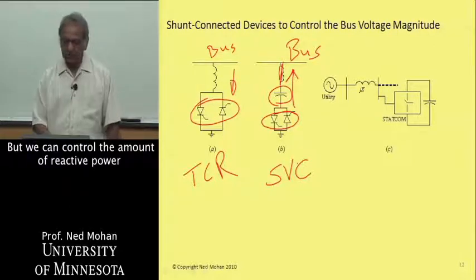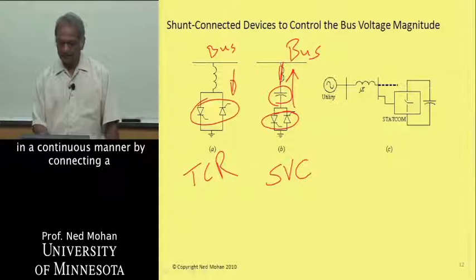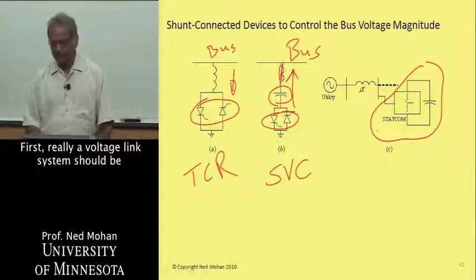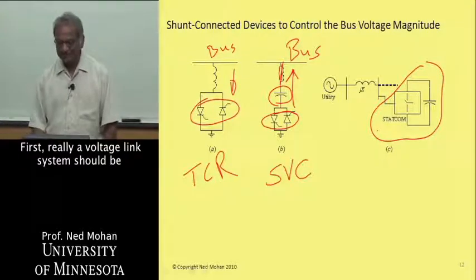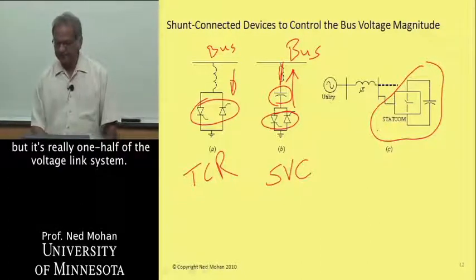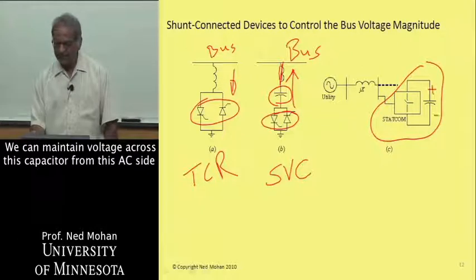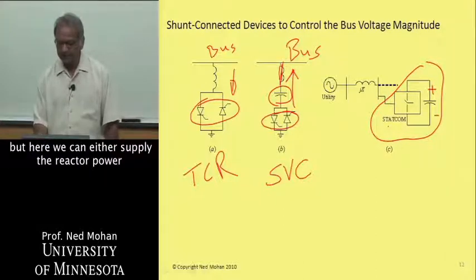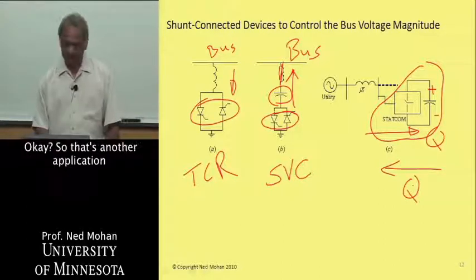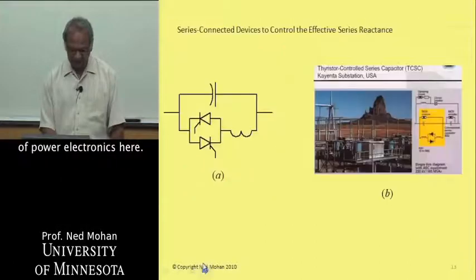We can control the amount of reactive power continuously by connecting a static compensator, or STATCOM. It's really a voltage-linked system, or one-half of a voltage-linked system. We can maintain the voltage across the capacitor from the AC side, and either supply or draw reactive power. It's a very flexible device and another application of power electronics.